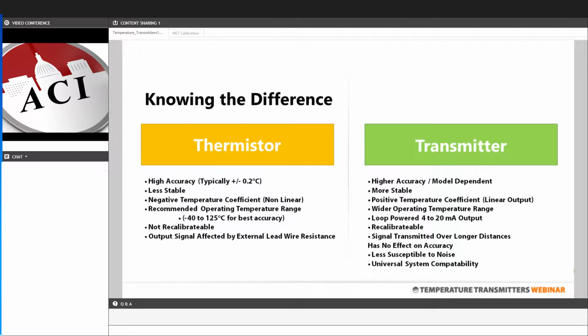Thermistors are more commonly used out in the controls industry, and transmitters provide a different type of output. Obviously, it's a current output versus a resistive output. And here's some of the differences or reasons why you would use a transmitter versus a thermistor. It's hard to say one is better or worse than the other. They're just different, and certain applications call for a current output, whereas others might be better suited for a resistive output. When using a transmitter, you can get a higher level of accuracy and a more stable output.